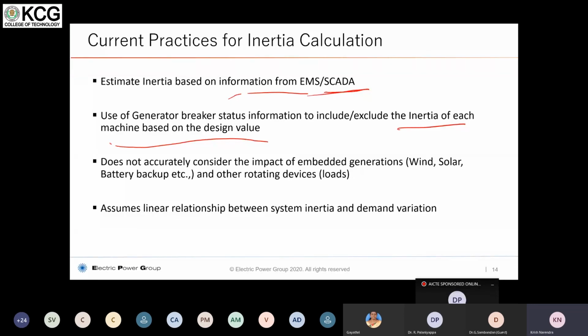The other aspect is that in most cases, since we take only the generator breaker statuses to include for the inertia, we are forgetting about embedded generation such as wind, solar, battery backup, and other rotating devices in your system, such as synchronous condensers and big induction motors, which have a very high impact of inertial support to the grid. All these things are not considered in the current practice. With the measurement mechanism through synchrophasor technology, you will be including all these aspects in the system, and therefore a measurement-based inertial response estimation is always considered superior to the estimation that is currently done. We also assume currently that there is a linear relationship between system inertia and demand variation, which is not correct in practice. Therefore, there are a lot of assumptions we make currently.